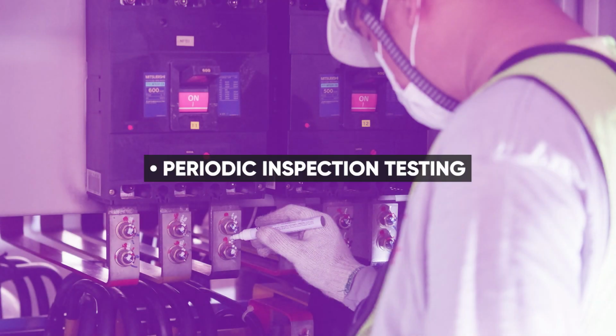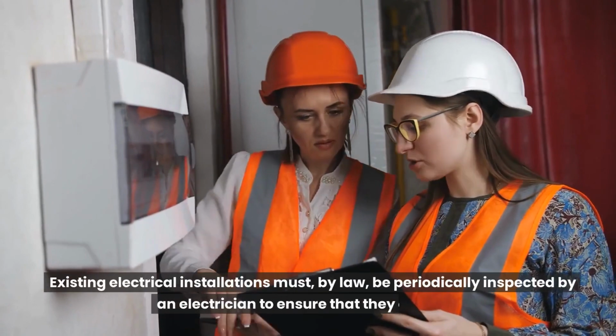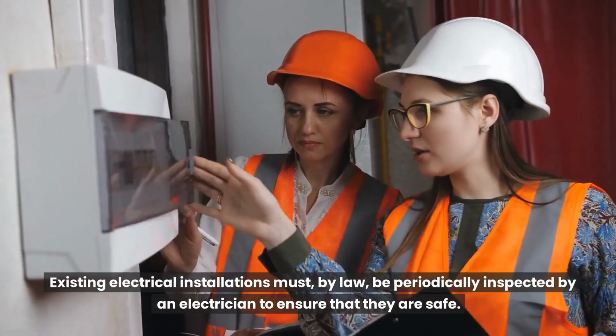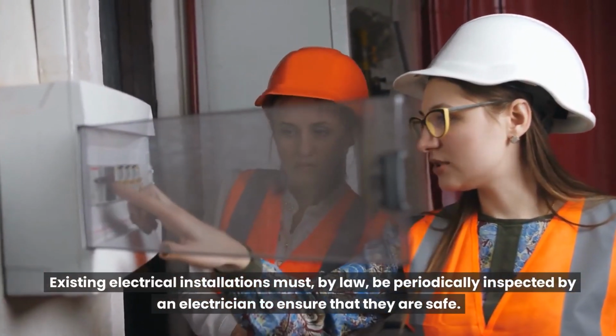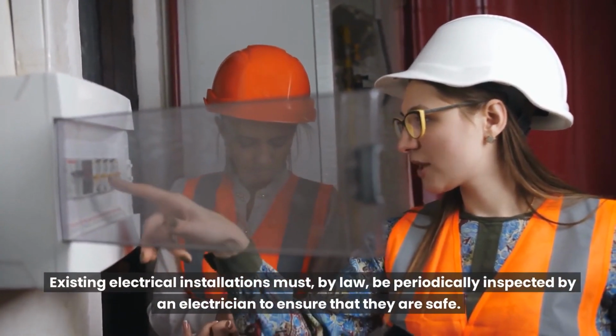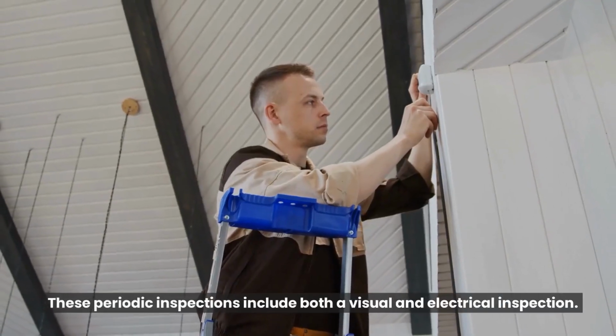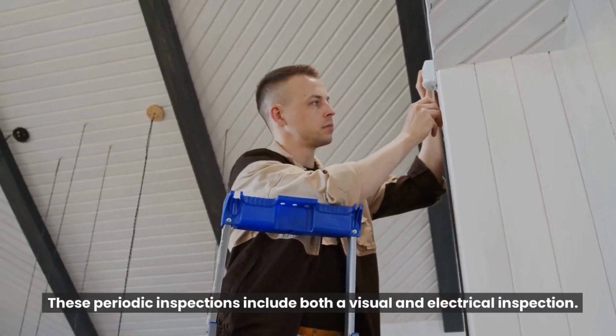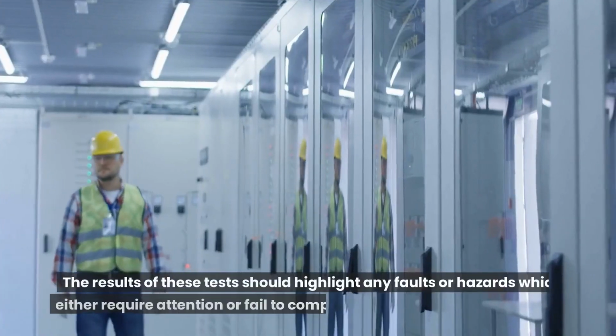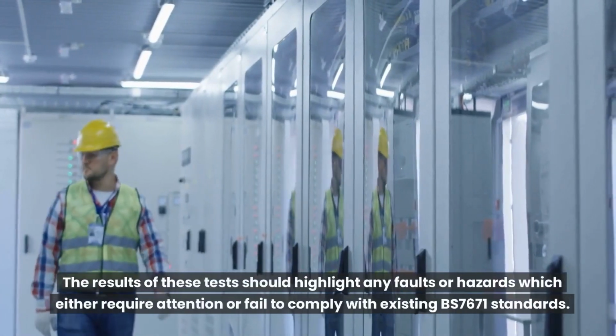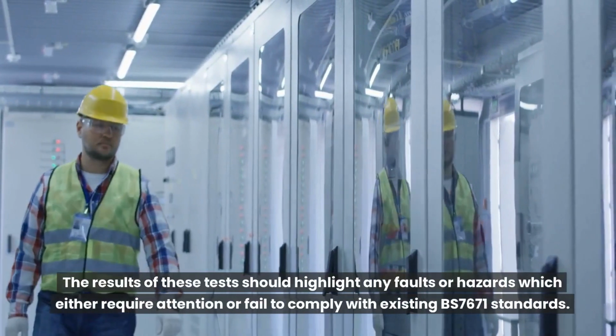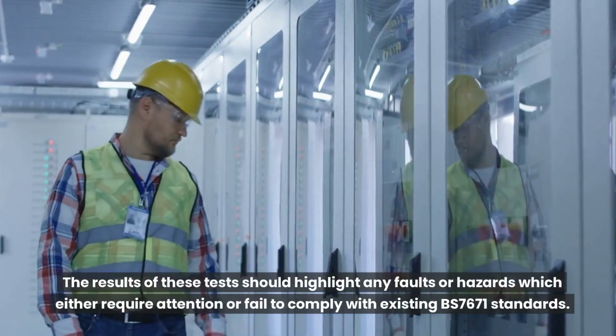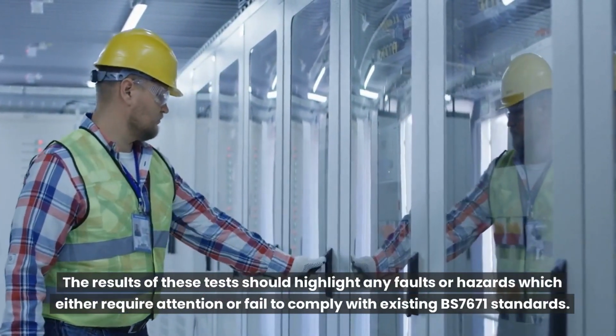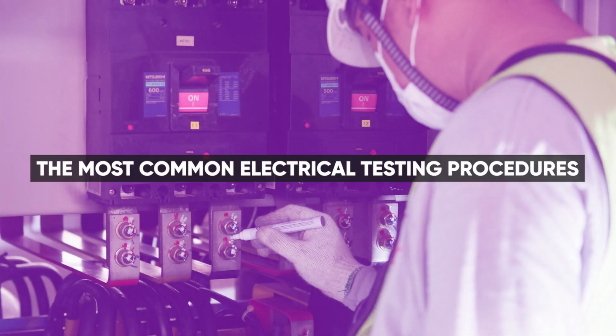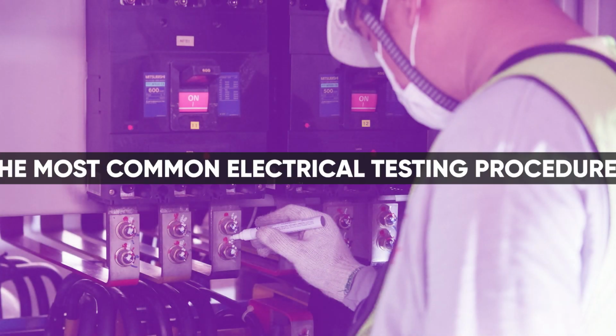Periodic inspection testing. Existing electrical installations must, by law, be periodically inspected by an electrician to ensure that they are safe. These periodic inspections include both a visual and electrical inspection. The results of these tests should highlight any faults or hazards which either require attention or fail to comply with existing BS 7671 standards. The most common electrical testing procedures.